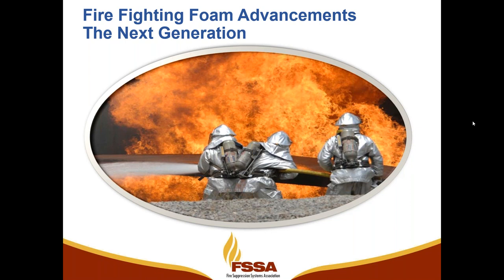So I've alluded to the fact that we also have products currently being developed, and already developed for sale and use, that are free of fluorine. These are called fluorine-free foams or 3F foams. You'll see a lot of different acronyms for them. But basically, we've had to find a way to take that fluorochemical out and get enough performance so that we can pass some of these same performance fire tests without having the advantages that the fluorochemical brings. And those two advantages, remember, were the formation of a film and also the fuel shedding characteristics, or oleophobicity. Next slide.